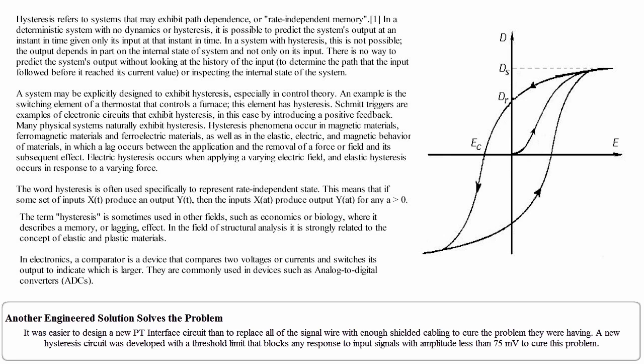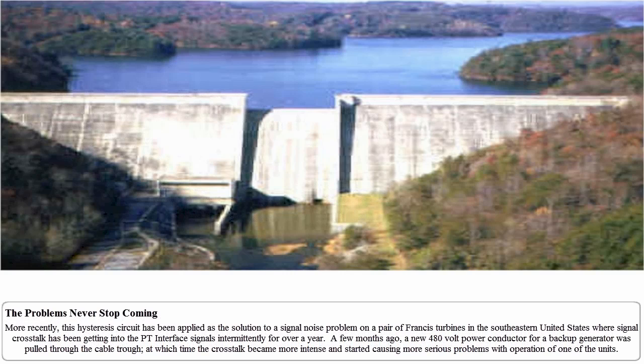A new hysteresis circuit was developed with a threshold limit that blocks any response to input signals with amplitude less than 75 millivolts to cure this problem. More recently, this hysteresis circuit has been applied as the solution to a signal noise problem on a pair of Francis turbines in the southeastern United States, where signal crosstalk has been getting into the PT interface signals intermittently for over a year.